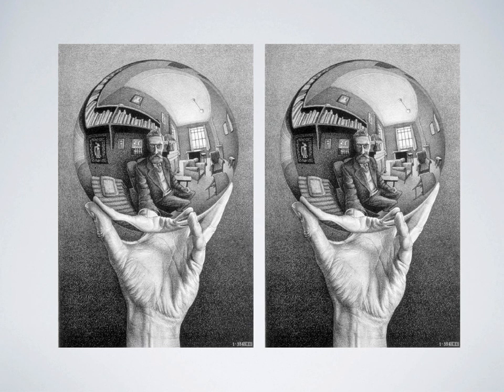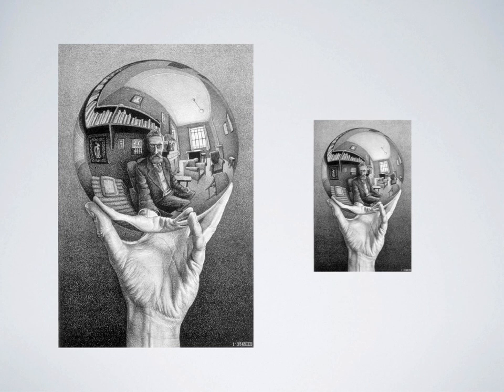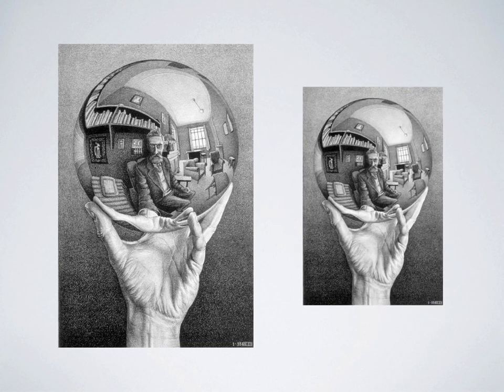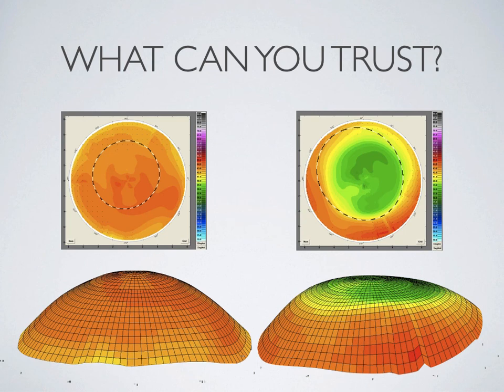M.C. Escher's self-portrait in a sphere illustrates how the same scene is compressed over a smaller diameter as the ball shrinks — analogous to how the keratometer's annulus shifts outward on a flatter post-refractive cornea. Keratometers and topographers don't actually measure dioptric power directly; they measure the radius of curvature of the anterior corneal surface, which is then converted to dioptric power.